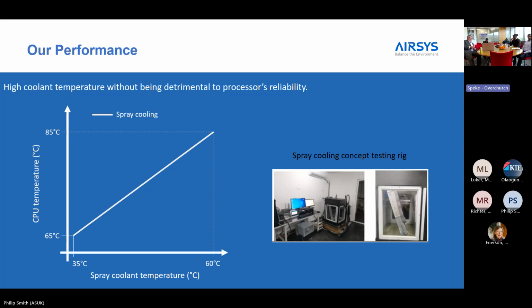The UK, it's more difficult, so they are sort of starting from scratch as to how they apply that heat. But the principle remains that by using liquid cooling, you have the facility to, A, get rid of any other form of cooling. You don't need CRAC units. You don't need big air handling units to cool the white space, cool the IT load, because it's all being directly taken from an enclosed environment and removed out. You may get a little bit of radiation from the box that the servers are in, but that's about it.